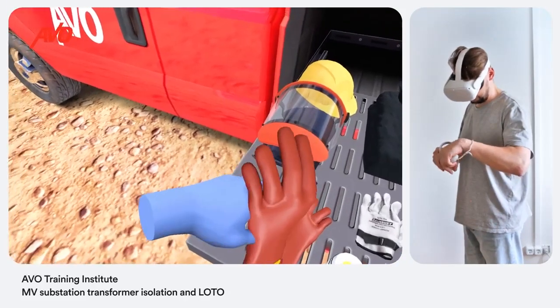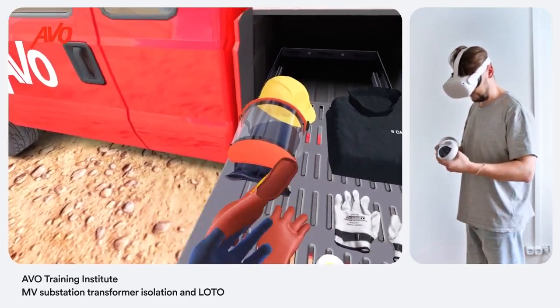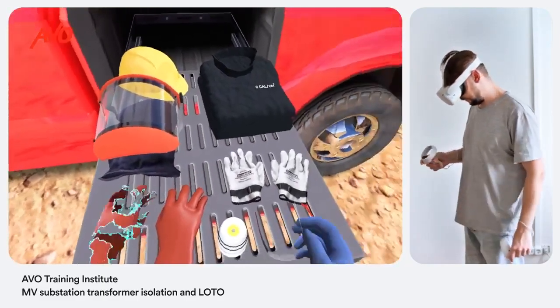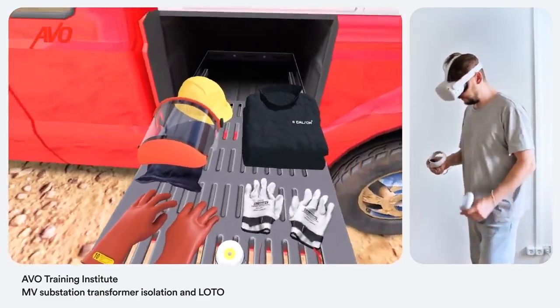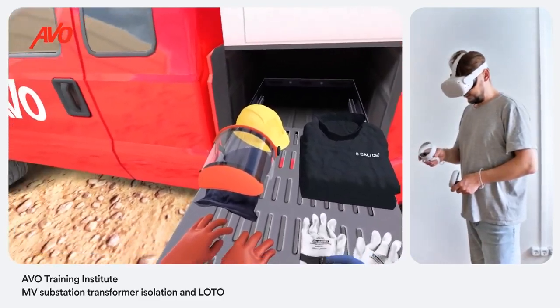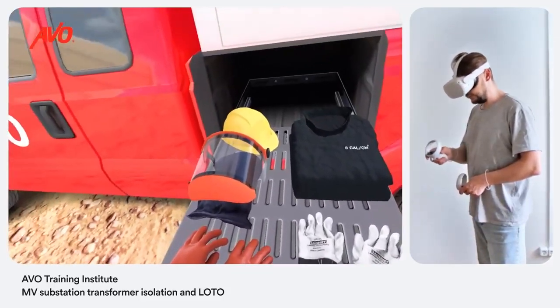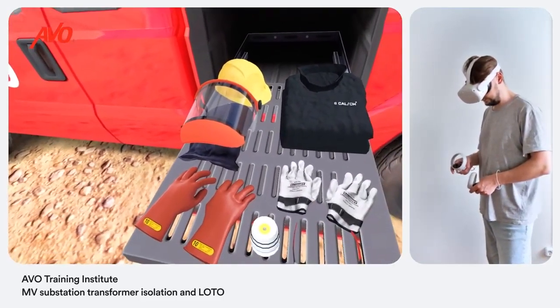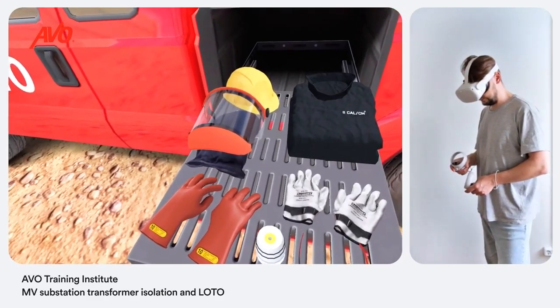Put on your personal protective equipment. Class 2 insulated gloves. Leather protector gloves. 8 calories per square centimeter arc flash coverall. Safety glasses. A hard hat, a face shield and a balaclava. Note that each item should be carefully inspected before use.